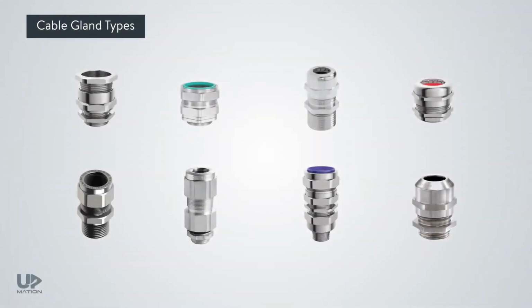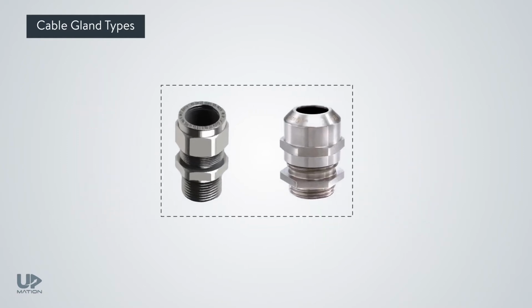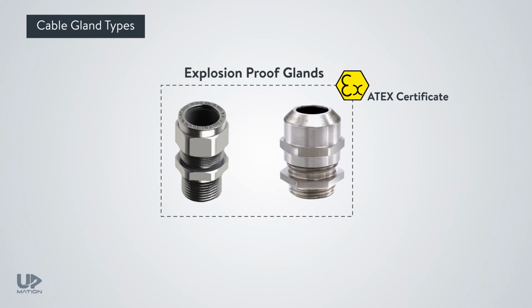There are different types of glands from type A to type E, and each is made for a particular purpose, which we will talk about later. Some specific types of glands are made for hazardous climate conditions and areas to prevent the entry of flammable gas or vapors into the enclosure of the equipment. These types have ATEX approval and are known as flame-proof or explosion-proof glands.